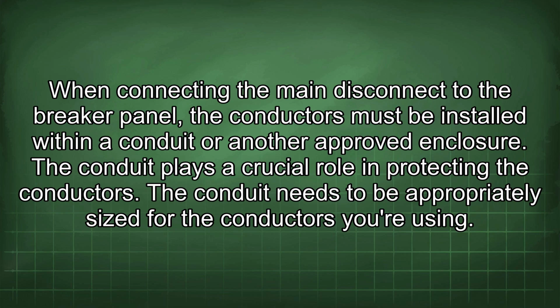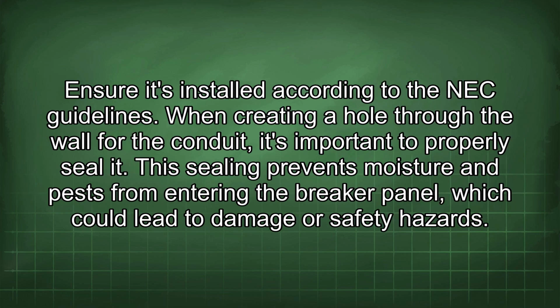The conduit needs to be appropriately sized for the conductors you're using. Ensure it's installed according to the NEC guidelines. When creating a hole through the wall for the conduit, it's important to properly seal it. This sealing prevents moisture and pests from entering the breaker panel, which could lead to damage or safety hazards.